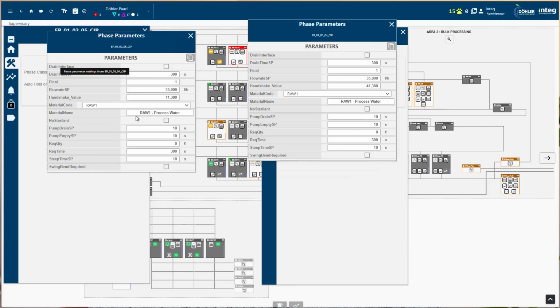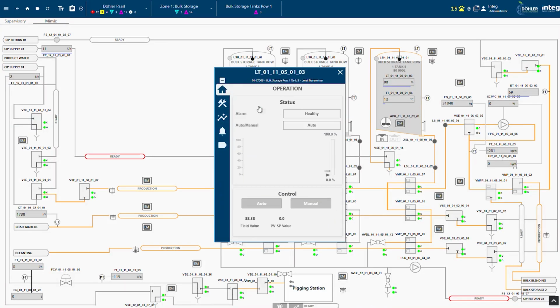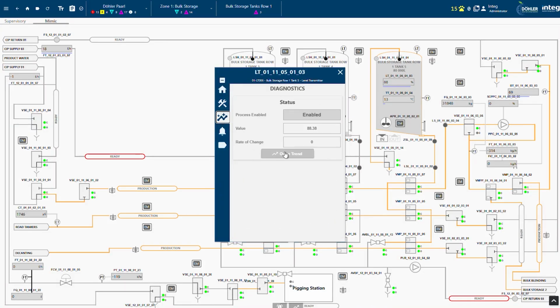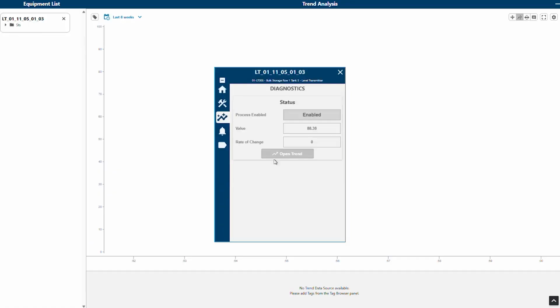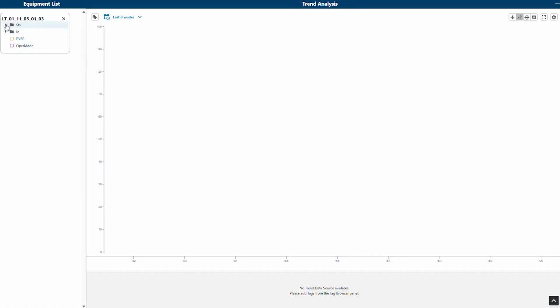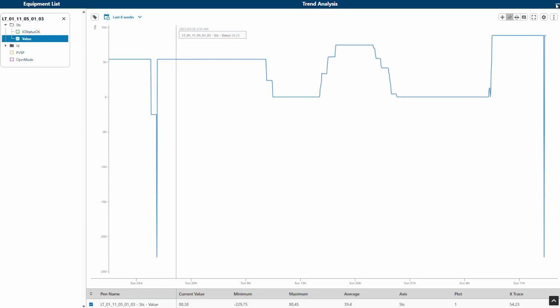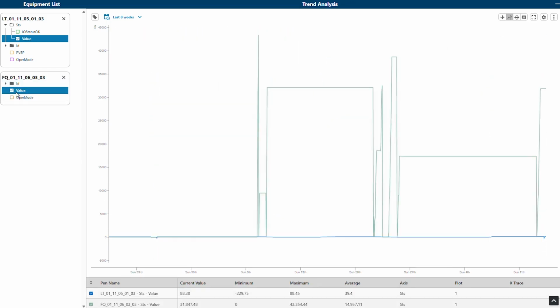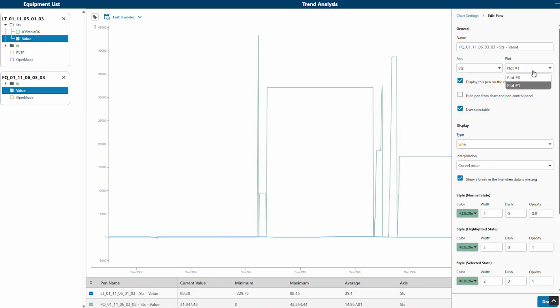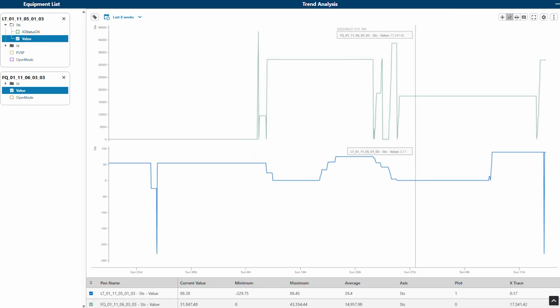With a trending tool, opening up a trend tool with a whole list of instrumentation on the left-hand side and having to go select certain instruments or values to trend is difficult, especially for people that don't know the plant. So we built a function where they could easily, from a faceplate, add those values onto the trend tool and build it from the SCADA interface instead of going to a specific page.